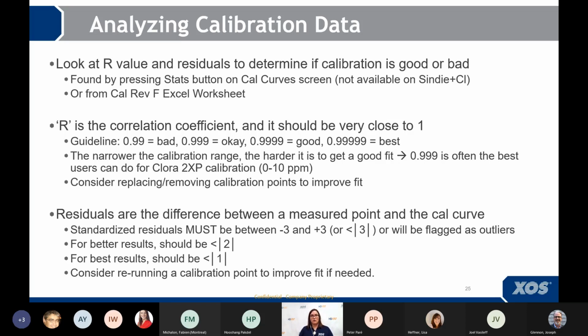Okay, R is your correlation coefficient. It should be very close to 1. So I talked earlier about how we're extremely linear. How linear? The guideline is that if you get 2 9s for your correlation coefficient, that's actually a bad calibration. You should get at least 3 9s, and you should aim for 4 9s or better to get the best calibration fit. Do note that the narrower the calibration range, the harder it is to get a good fit. So oftentimes for the Clora 2XP that uses a 0 to 10 ppm calibration, 3 9s is often the best that can be gotten because that calibration range is smooshed.